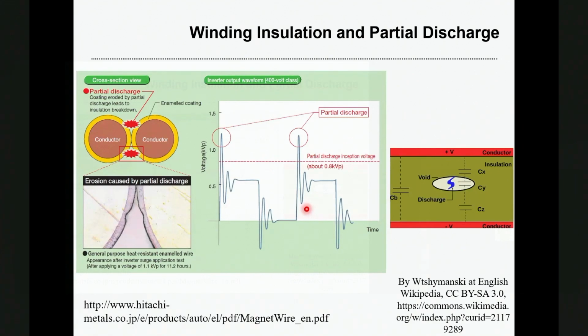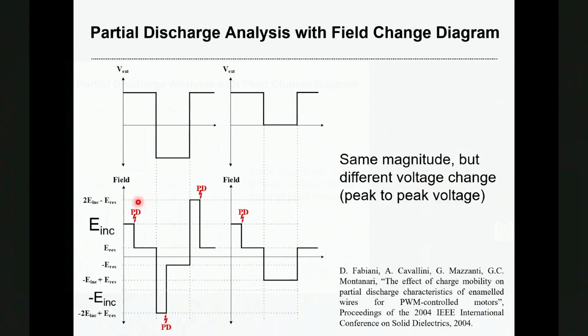So this overvoltage will cause the winding insulation degradation through the partial discharge effect. Basically, if the voltage is higher than the partial discharge inception voltage, it will trigger a partial discharge. And this partial discharge effect will eat up some of the insulation material, and over time, it will cause the insulation breakdown. In order to analyze what kind of waveforms will trigger a PD, that is partial discharge, you can use the so-called field change diagram to analyze that.